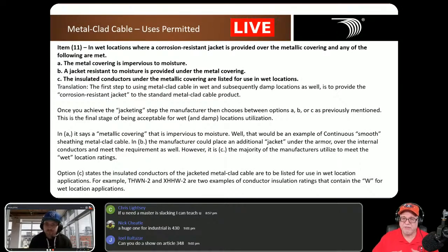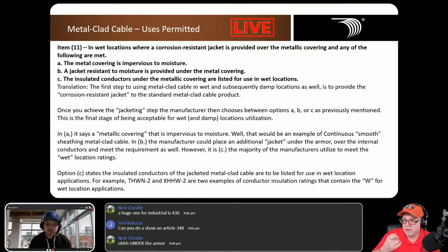So that would be, you have the conductors, then you're going to have a jacket of PVC material or whatnot over top of the conductors, and then you put the armor over it. So you're going to have a corrosive resistant jacket over the armor, and then in that case, underneath it, you have another jacket that is over the inner conductors. Okay? And ironically enough, those inner conductors would not have to be rated for a wet location if you use B as an option.